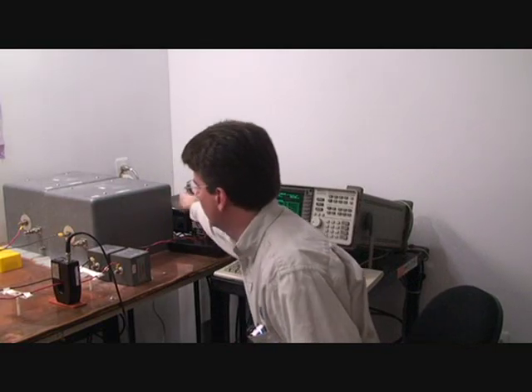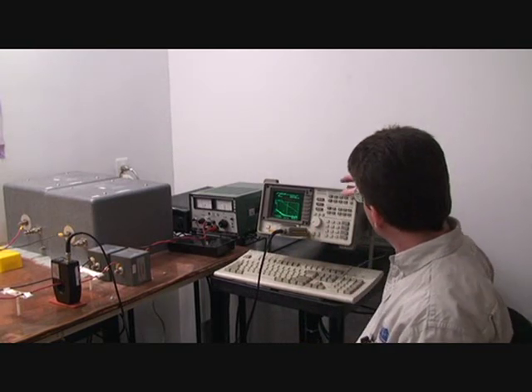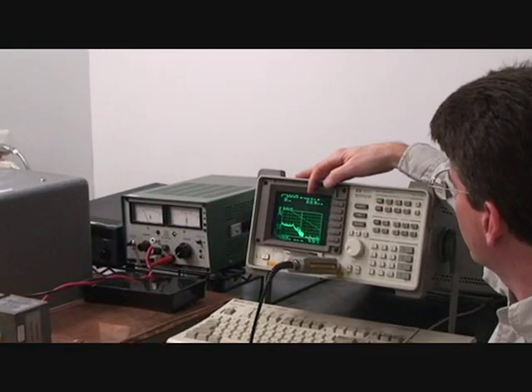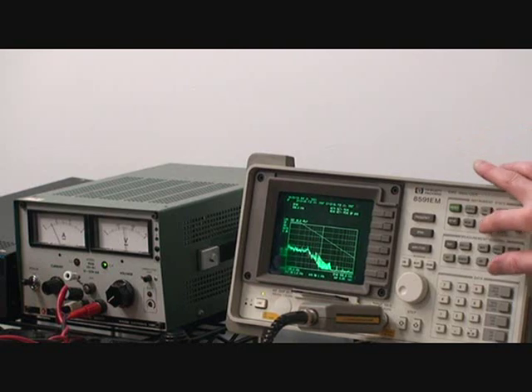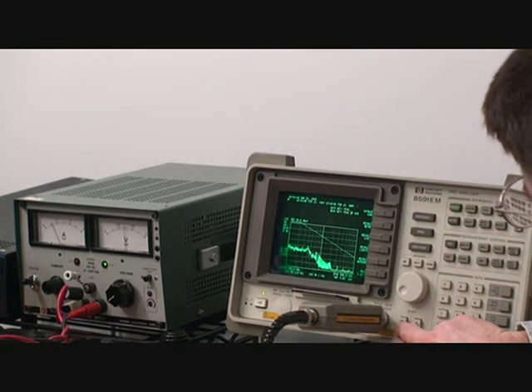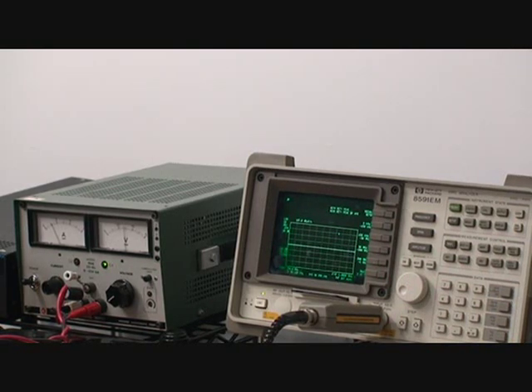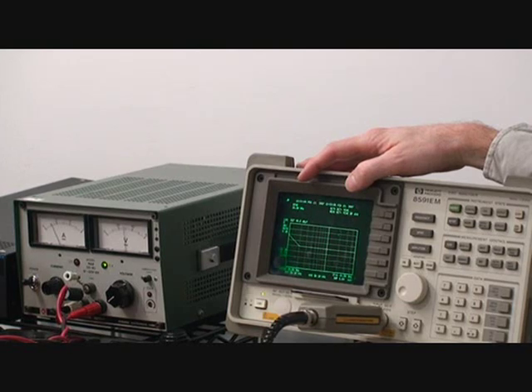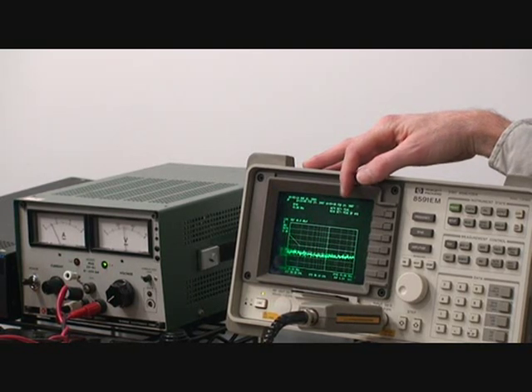Now we'll take a look at the actual 461C measurement. So first we'll turn the unit on. We have loaded on the EMI analyzer the low frequency band up to one megahertz. We'll go ahead now and take a sweep. You can see it sweep across the bottom of the screen and the limit line is on top. The emissions of the DVTR are well under the limit. Now we will load the higher frequency portion of 461C. It will go ahead and take a sweep. Again you can see the measurement sweeping across the bottom of the analyzer screen, well below the limit line.